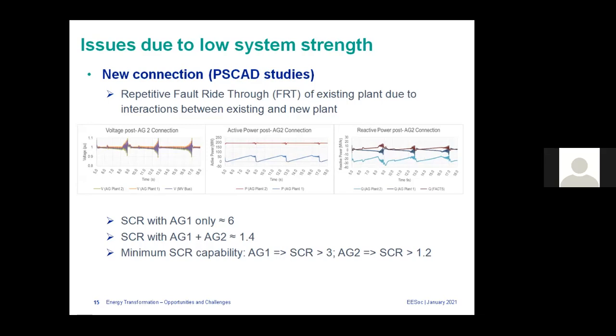So what we did, we found a solution for this issue. We went and tuned these solar farm inverters. So we managed to get it over, and now we have the full solar farm and wind farm generating without any issue because the solar farm inverters were tuned. They changed their inverter controls and power plant controls. So we managed to get a stable response after that tuning of the generation.